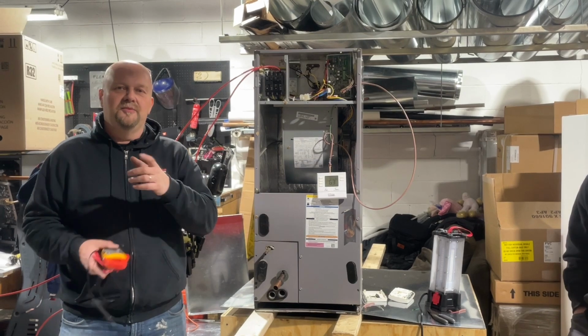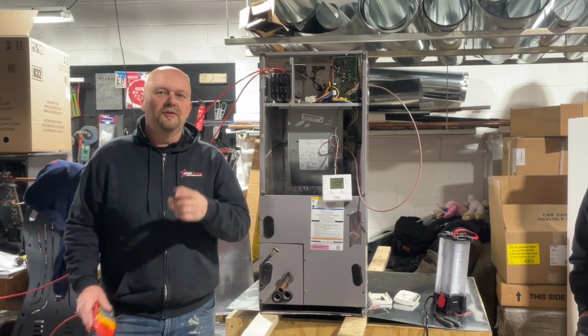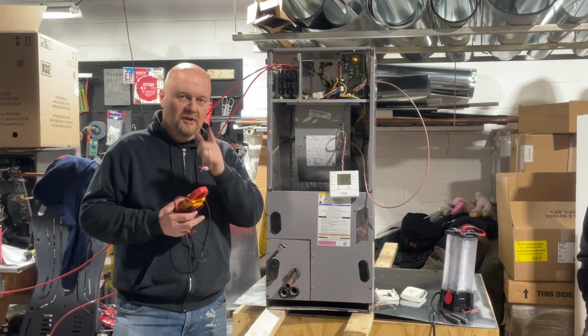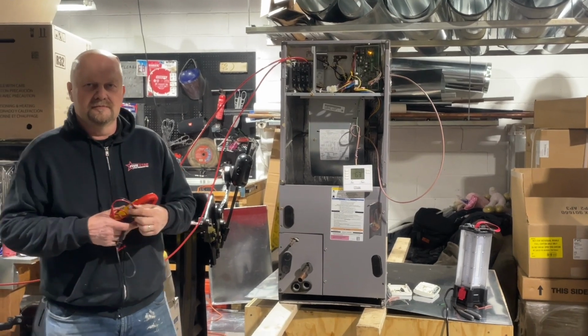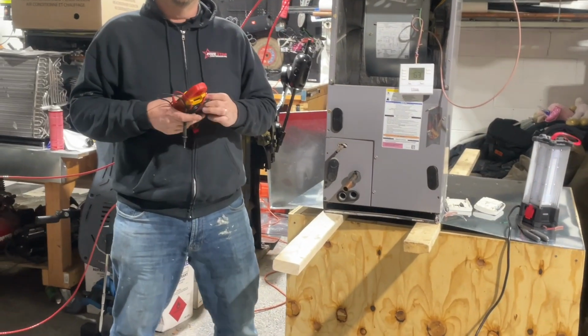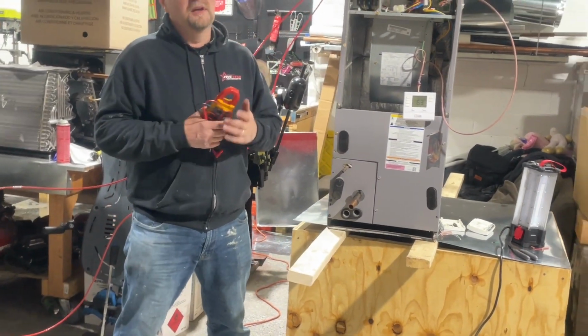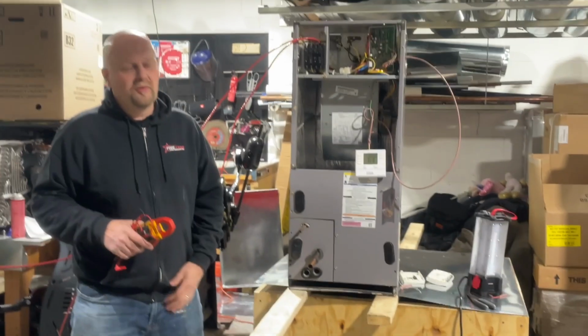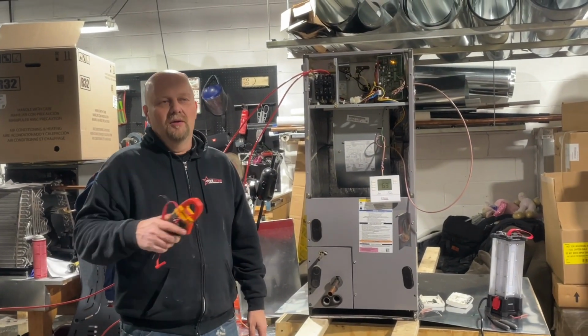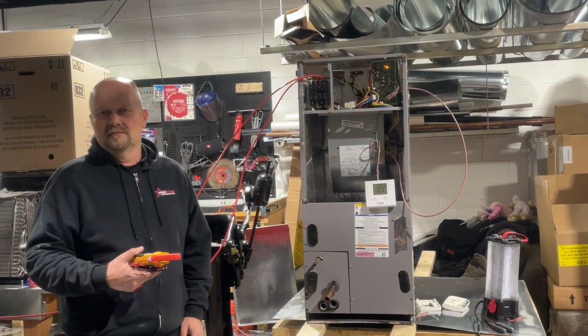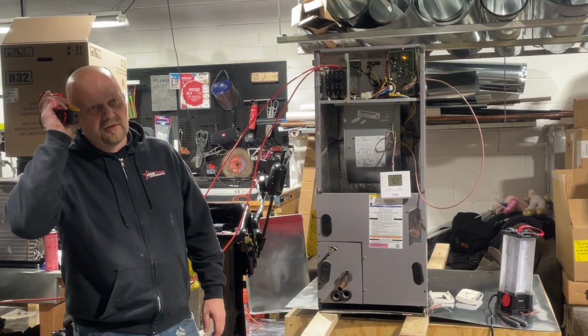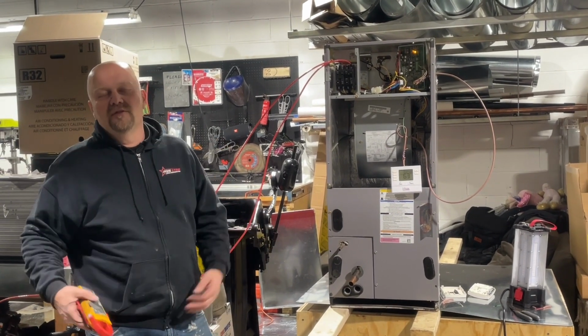And actually, as a matter of fact, Peter, on the next dual fuel job we're going to sell, we're going to install a coil on the return. Coil on the return? Yeah. We're going to install it on the return, and we're going to put the furnace on top of it. Where's the filter? It's got to be underneath the coil, because you've got to protect the coil. So that still remains the same.